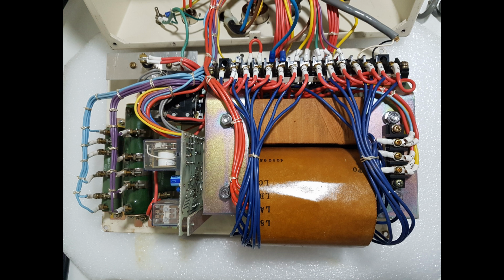To the left of that are two green items with some wires connected to them. These are resistors that are used to calibrate the instrument. They adjust the mA. This unit is called a falling load X-ray machine. By changing the mA, we can balance out the kV on this one. It's like a seesaw. When the mA gets increased, the kV will decrease to reach the balance point again.